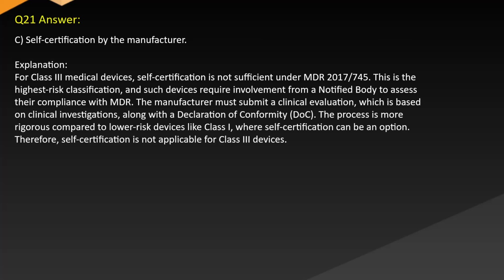Explanation: for Class III medical devices, self-certification is not sufficient under MDR 2017-745. This is the highest risk classification, and such devices require involvement from a notified body to assess their compliance with MDR. The manufacturer must submit a clinical evaluation, which is based on clinical investigations, along with the declaration of conformity document. The process is more rigorous compared to low-risk devices like Class I, where self-certification can be an option. Therefore, self-certification is not applicable for Class III devices.